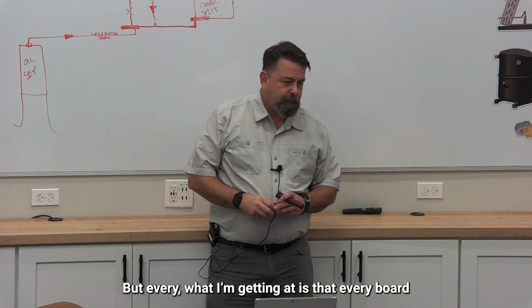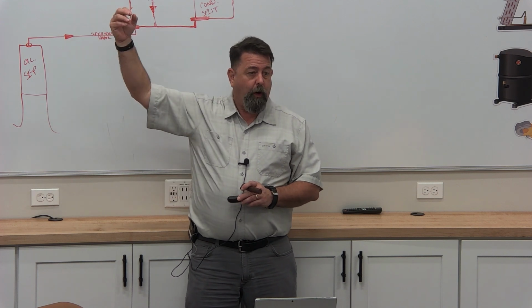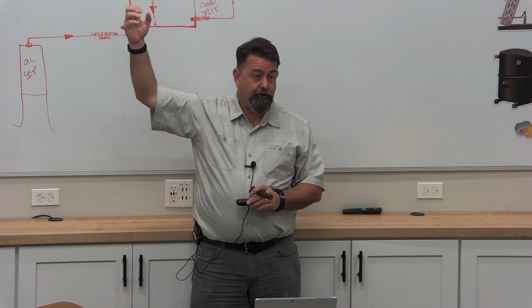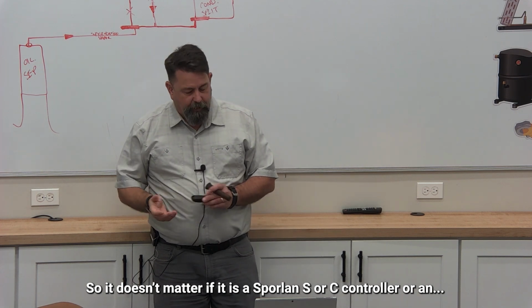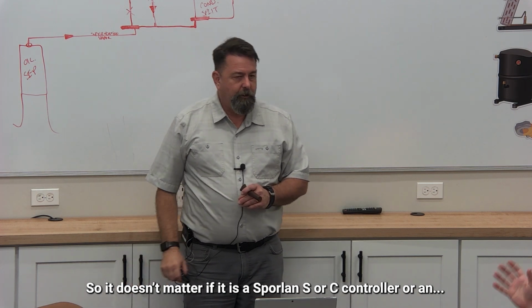What I'm getting is every board manufacturer does that. Yes. So modern Novar, the XIO 1081, drives a valve itself - it's a Novar component, and it's built into that program to drive it 10% too far. So it doesn't matter if it's a Sporlan S or C controller or a Novar 1081, they all do it.